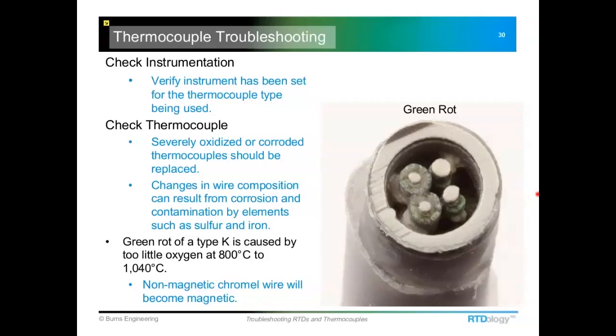Other issues with thermocouples include making sure your instrumentation is set to the correct thermocouple type. The most common base metal thermocouples are types J, K, T, and E. Each one has a different temperature-to-millivolt relationship, so you need to make sure the settings are correct in your transmitter or signal conditioning equipment to accept that type thermocouple.